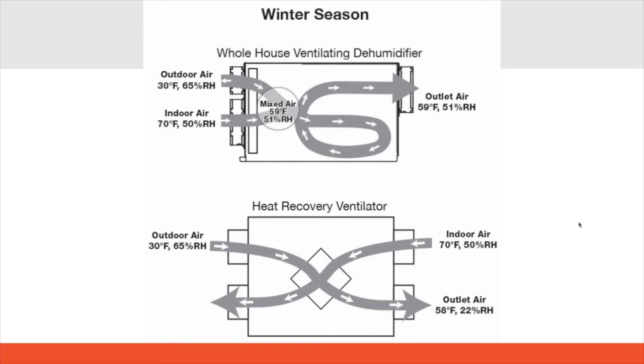So in this illustration here, the top is showing one of our heat recovery ventilator dehumidifiers. The outdoor air is 30 degrees and the indoor air on the left-hand side is 70 degrees. We're going to bring in the outdoor air and that return air into the dehumidifier, mix it, and then our outlet air is going to be 59 degrees. So it's not 30-degree temps that we're delivering to the living space. And as you can see below, where we just use a heat recovery ventilator as the illustration, because again, we're not doing any active latent exchange here, the outdoor air coming in is 30 degrees and the outlet air into the space is 58 degrees. So not far off in temperature there.